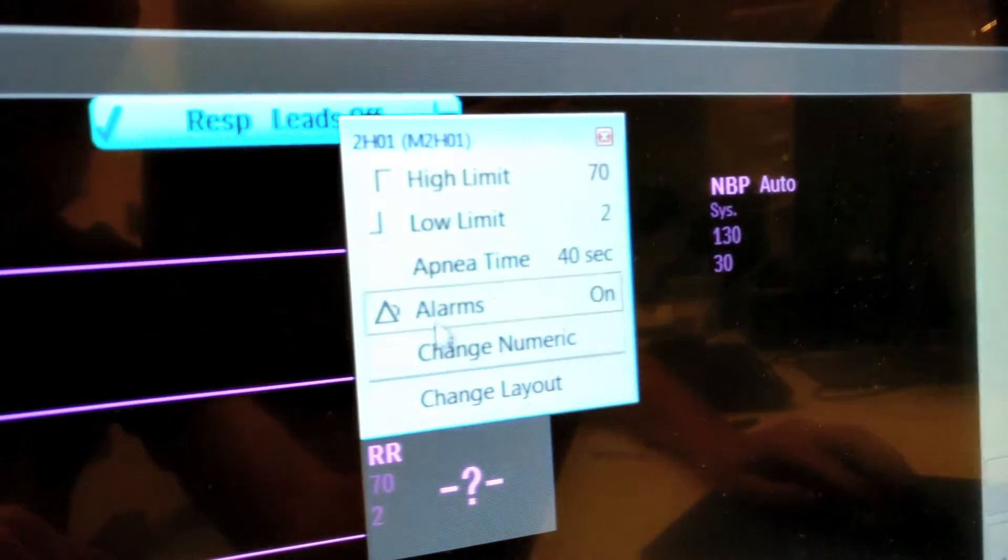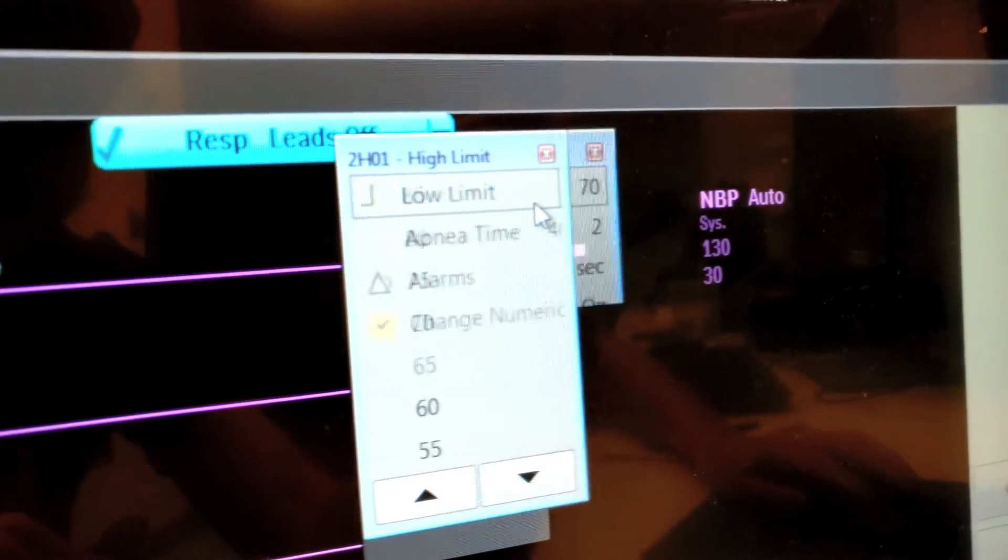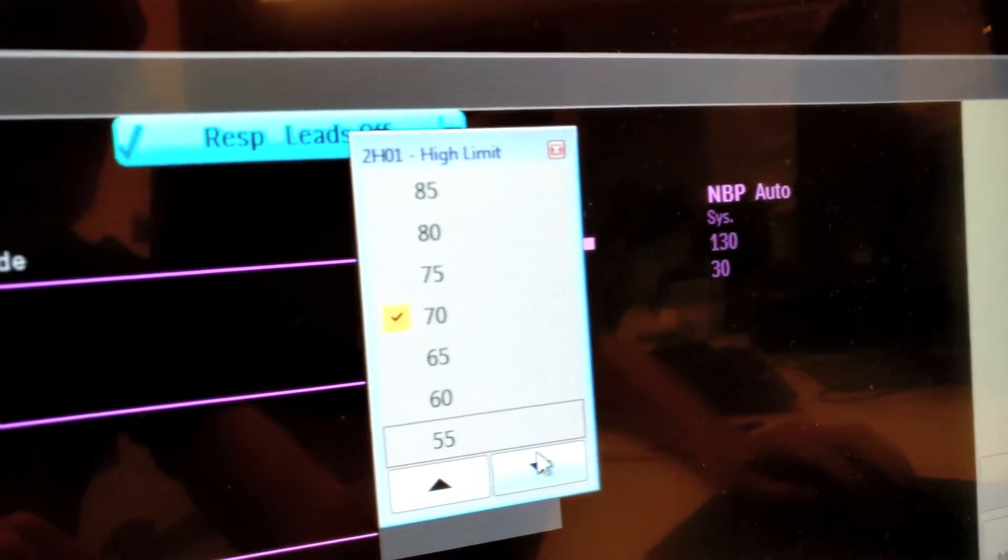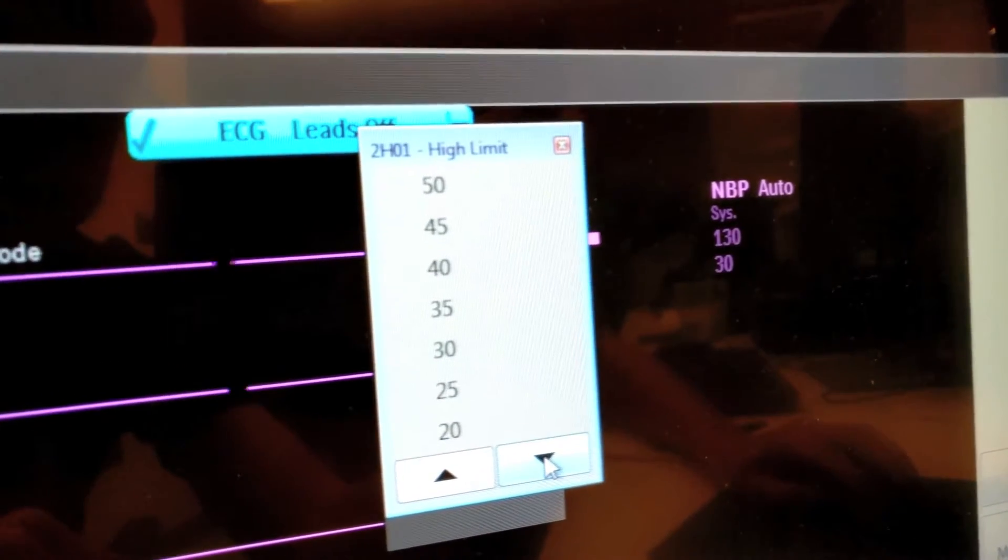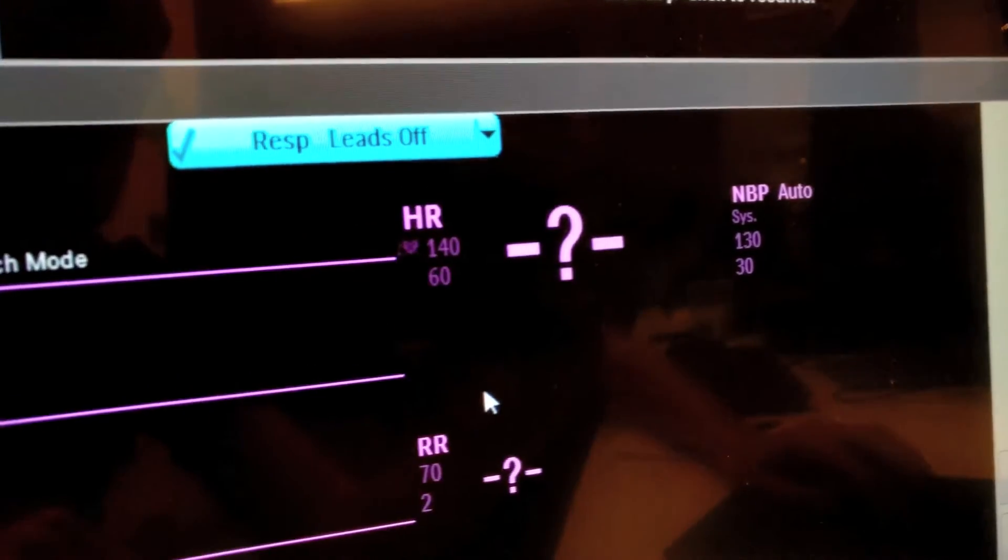Also make sure appropriate alarms such as the irregular heart rate and AFib alarms are turned back on. All alarms will still ring at the nurse's station if you set them, but they will not sound in the patient's room.